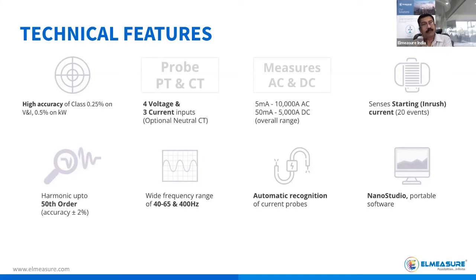The harmonics can go up to 50th order as against 25th order what we're talking in Nanoweb 1. And then the frequency range can go up to 400 hertz, in addition to 40 to 65, can go up to 400 hertz. And again like Nanoweb 1, this can also recognize the CTs you're going to connect. Same CTs, 5 amps, 200 or 1000 clamps, or 3000 or 6000 flexi CT. Anything can be used in this particular product.